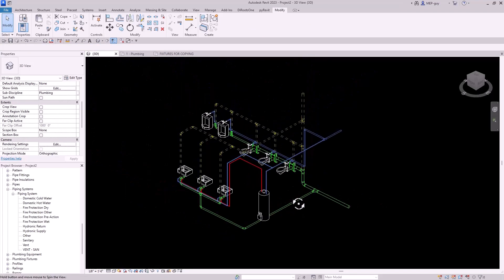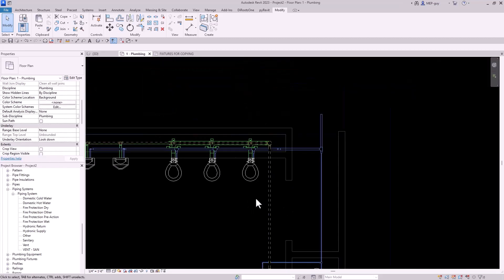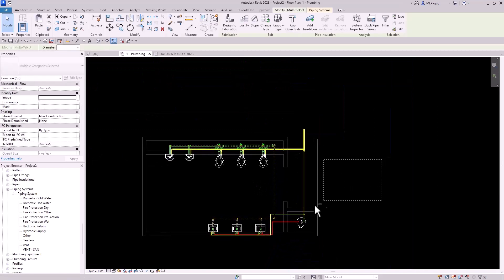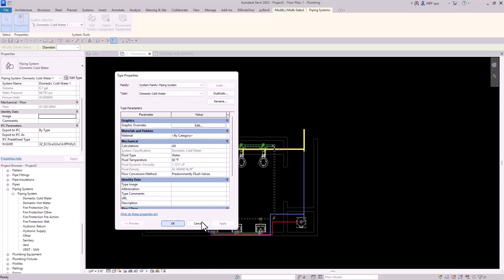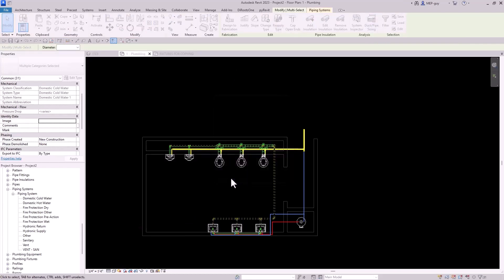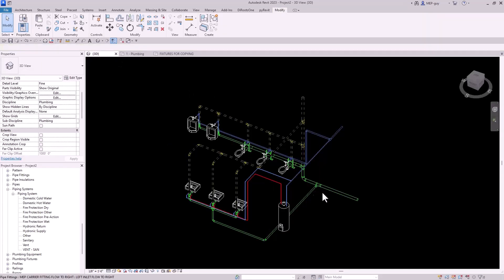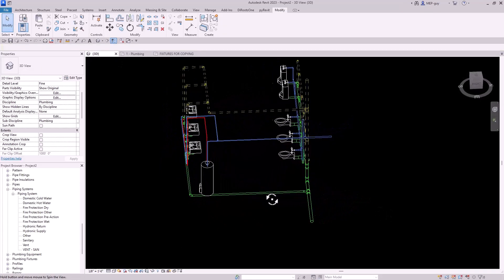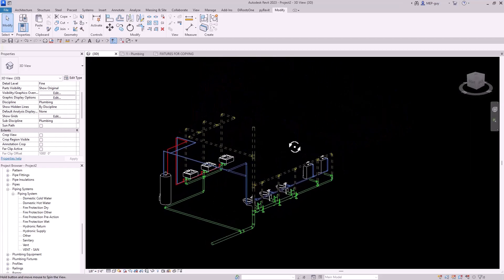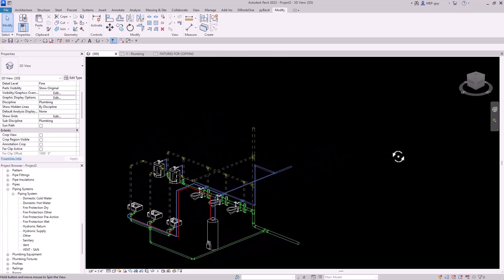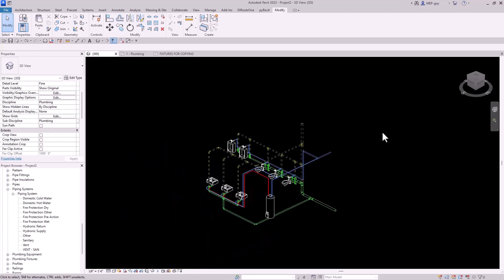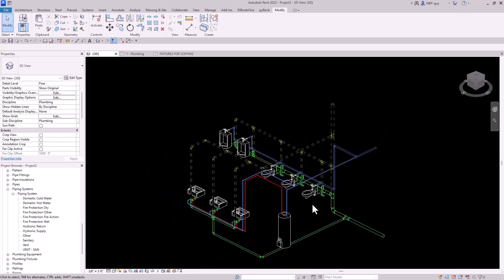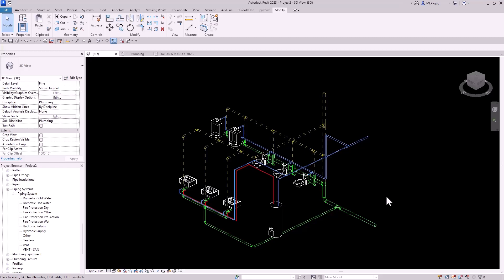One last thing before we finish: let's make sure we size this cold water piping correctly. Let's go to the first floor plan, tab into all these pieces, deselect what we don't need, and size this for a flush valve type system. We'll go to piping systems, make sure we have flush valve selected, go to our duct pipe sizing tool, and click OK. Now we've essentially sized this water piping. Let's go back to the 3D view and really take a look — we've modeled this entire plumbing system in a very short amount of time. What I really wanted to demonstrate is the power of these custom plumbing fixtures, which you can get at MEPGuy.com. They come with my course Plumbing 101, where I go over modeling a complete plumbing system from scratch, creating custom plumbing fixtures, and everything you'll need to know for plumbing design inside Revit. If you want to check out more insanely fast plumbing videos, make sure to check out the next one. Thanks guys, bye.